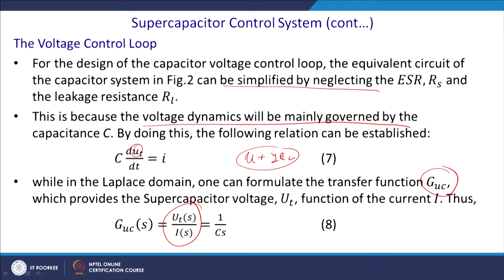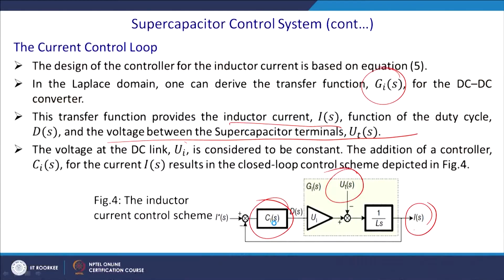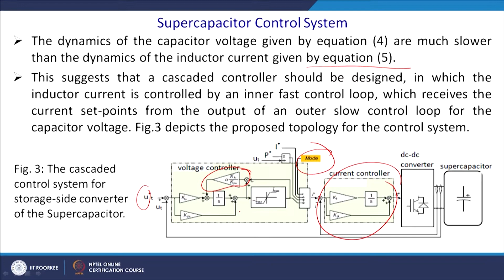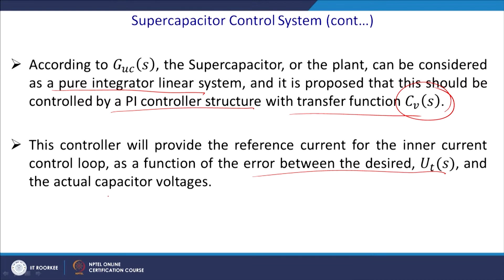So, according to this Guc, the supercapacitor or the plant can be considered as a pure integrator linear system, and it is proposed that this should be controlled by a PI controller structure with the transfer function of CV. By this analysis we now understand what kind of controller is required here. This is CI and we require another controller. So, we have to go back to this slide. This is basically the voltage controller, and what you can see is that it is a PI controller. This controller will provide the reference current for the inner current control loop as a function of the error between the UT reference and the actual capacitor voltage.